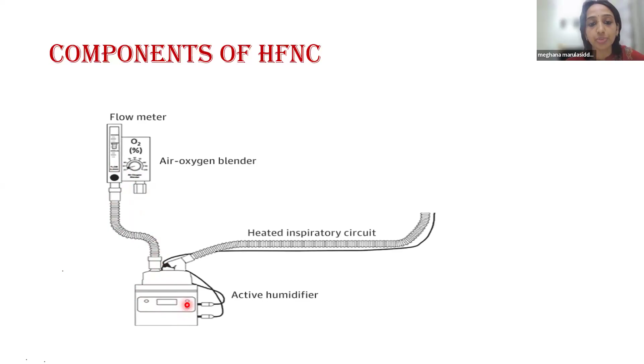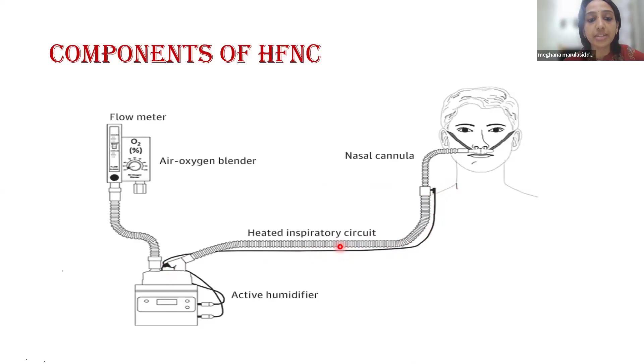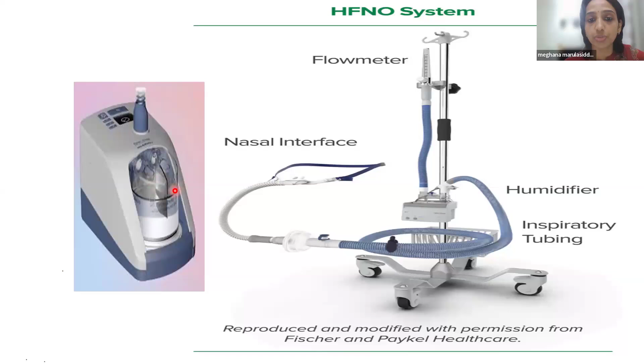You can also see here a temperature sensor. One is present at the humidifier end and the other temperature sensor is present at the patient end. This wire that is shown here is shown outside only for representation purposes. In reality, in the actual machine, it is inside this circuit. This is the actual HFNO apparatus. You can see here, this is a picture of the humidifier. This humidifier needs to be filled with sterile water, not normal saline, but distilled or sterile water, about 100 to 150 ml, depending on the instructions of the maker. You can see here, this is the patient interface, that is the nasal cannula, and this is the humidifier sitting on the heating plate, and these are the controls for the temperature.